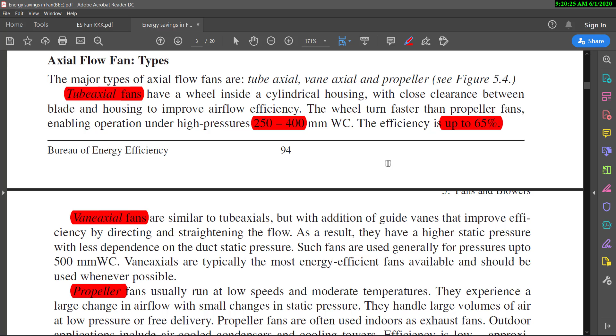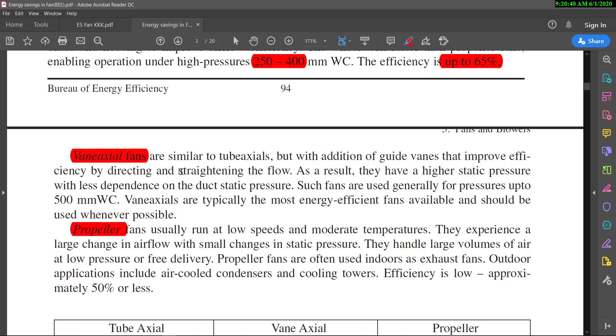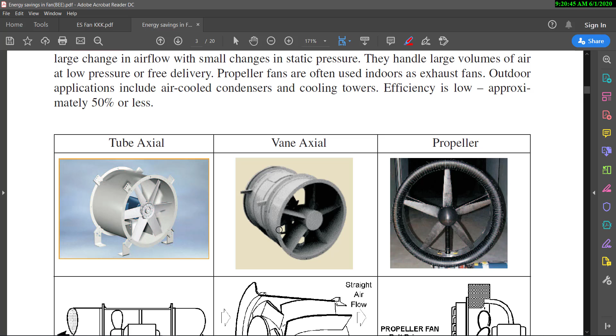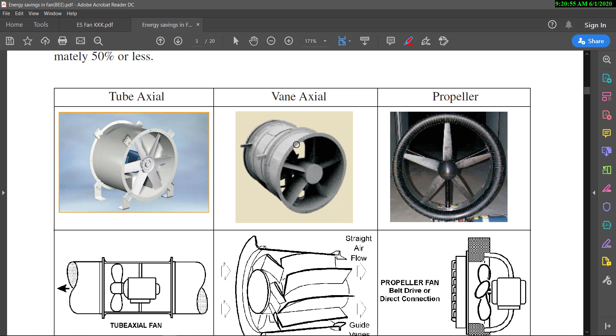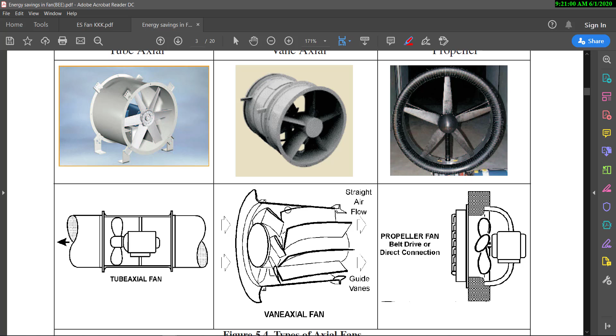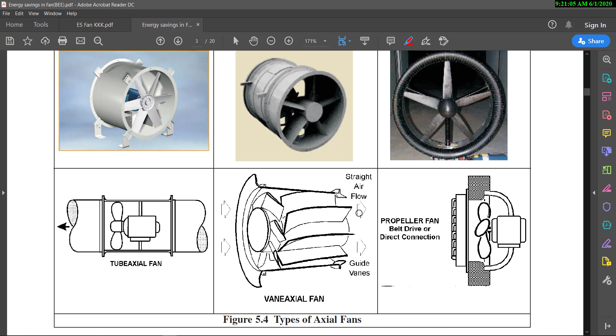And the second one is vane axial, which has an addition of guide vanes that improve efficiency by straightening the flow. This is the vane axial, the second type of axial fans. It is also like tube axial, but the structure is a little bit different. Straight airflow is available, that is one of the characteristics, and guide vanes are available. It is the most energy efficient fan available, and it should be used whenever possible. Based on our needs, we can use this type of fan.